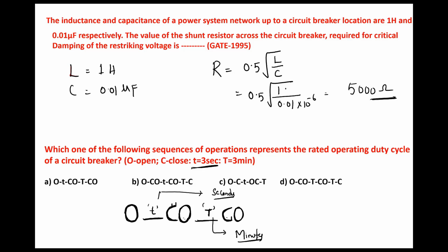Because we know that when a fault occurs, a huge amount of mechanical and thermal stresses are developed, a huge amount of magnetic forces and heat is generated. We should give some time for the circuit breaker to recover. Time is provided for dissipating heat.